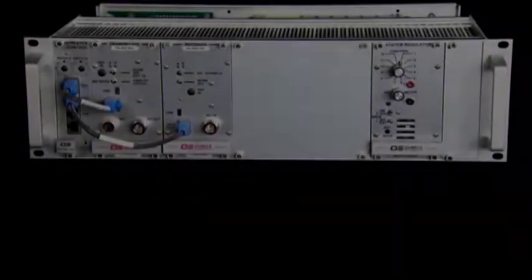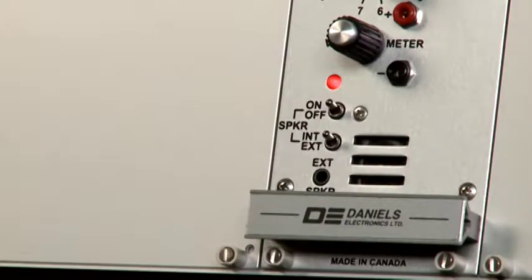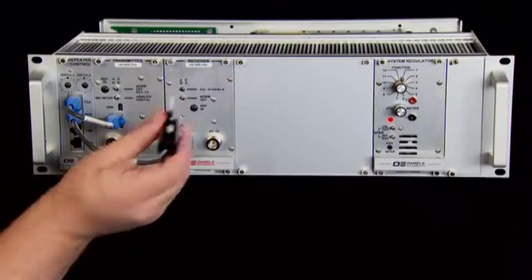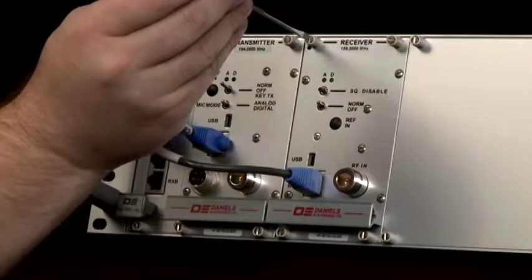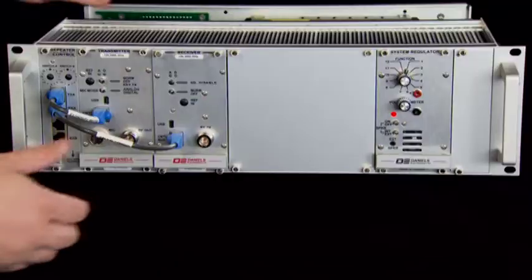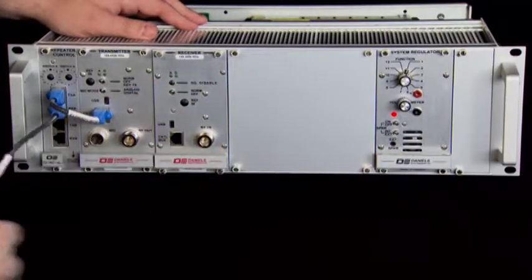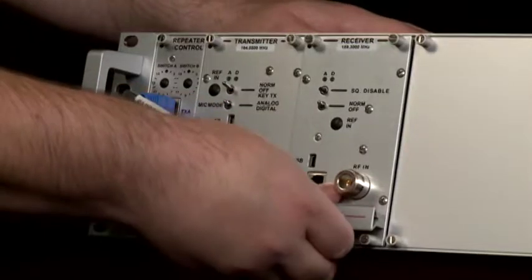To begin, ensure that the sub rack has power by turning the speaker switch on the system regulator to the on position and checking that the LED turns on. Turn the four quick release fasteners on the receiver 90 degrees counterclockwise to release them. Remove any RJ45 cables or RF cables connected to the receiver. Pull the receiver out of the sub rack.